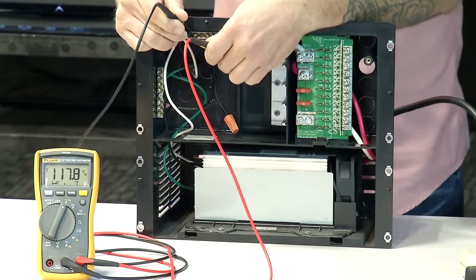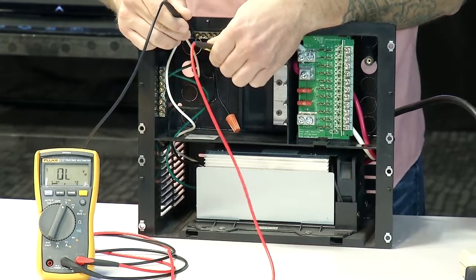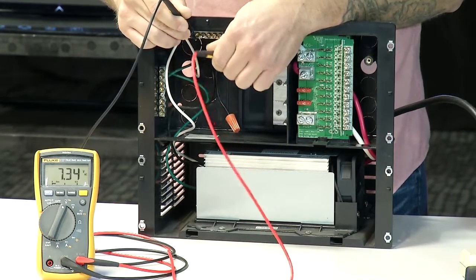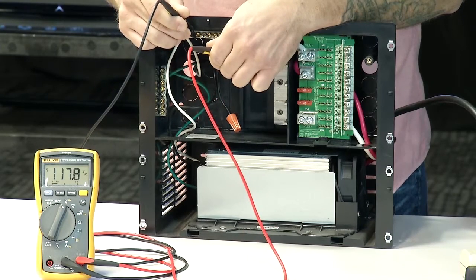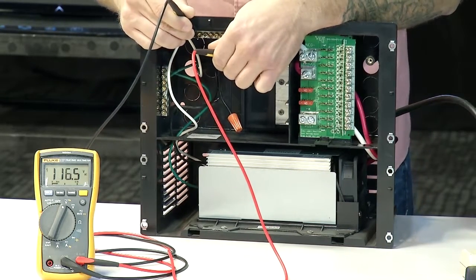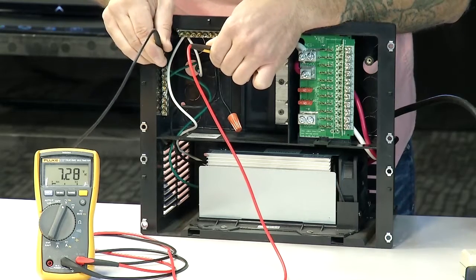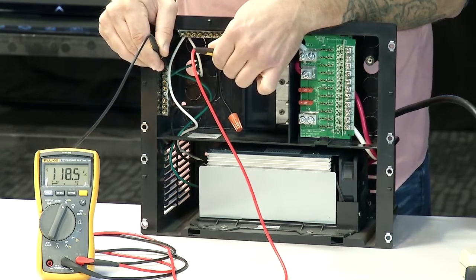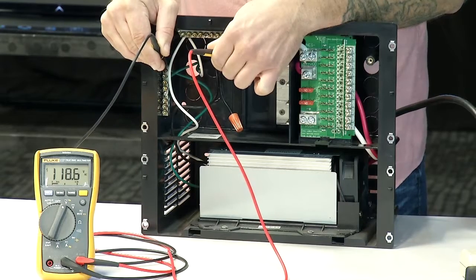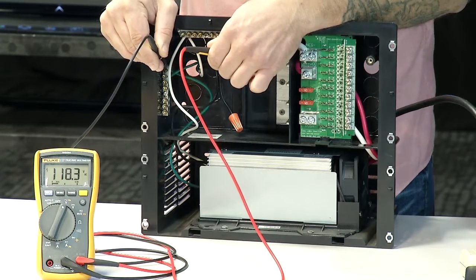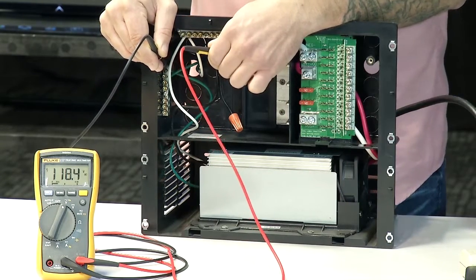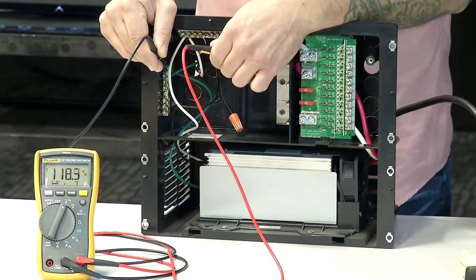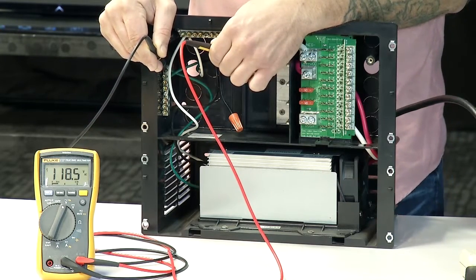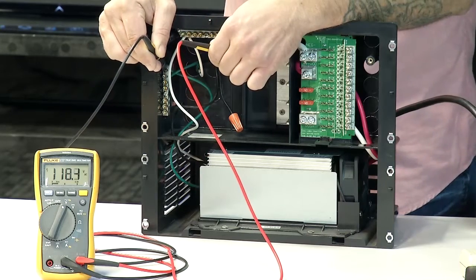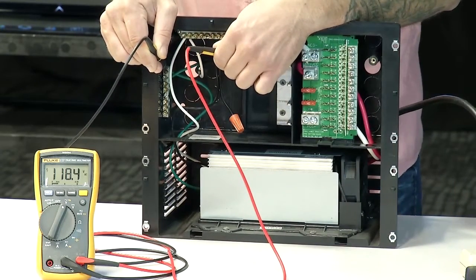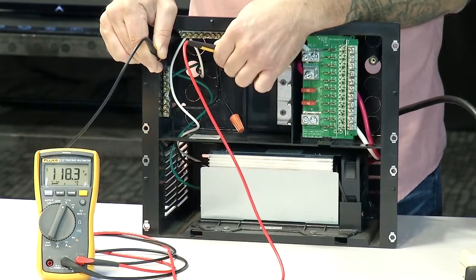And when you're checking your voltage, you want to check from AC hot. So AC hot is going to be your main breaker, to the neutral bar, which is the white wires. And you're also going to want to check hot to ground, which is your green wires. Should have around the same voltage, which I actually have a little bit higher on my ground bar, which is fine. But if you're getting a low reading on your AC hot to ground, that could indicate a bad ground. So you always want to check AC hot to AC ground, because if you're losing a ground, that can actually affect some of your products or the converter as well.